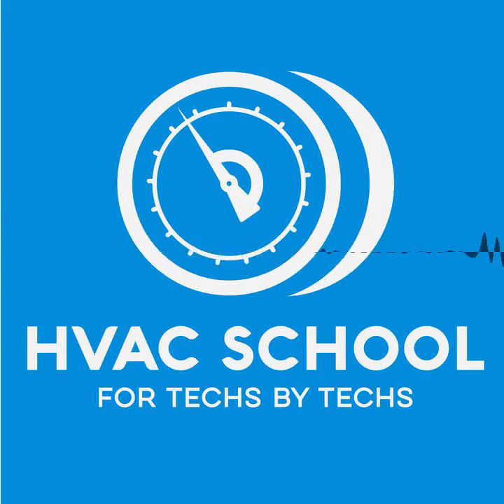Rarely do I see that the actual valve itself is just literally something wrong with it. It's almost always something external to it, with vibration being thrown into that same category, where it vibrates and then ends up cracking the bulb tube. Yeah, and the vibration isn't an issue only for TX valves. I mean, pressure controls and temperature controls, even connections on compressors are under that direct attack all the time by vibrations in the system. So yes, absolutely.